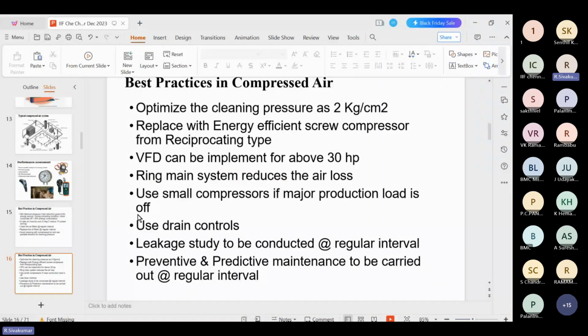And VFD can be implemented for air compressors above 30 HP where there is a large variation in loading and unloading, with more than 25 to 30% unloading. The VFD option is the best option. And a ring main system reduces the air loss. Use a small compressor if the major production load is off. It is particularly useful on Sundays, when maintenance activities are going on. During that time, there is no need to run the bigger compressor.